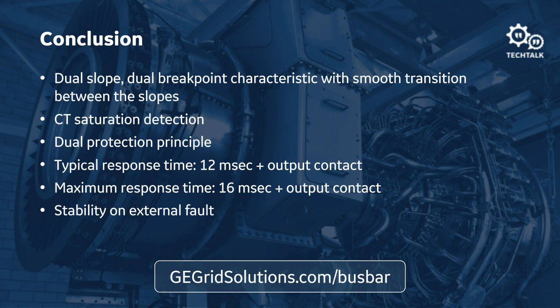Can we do breaker failure protection for each terminal? If you use the low impedance scheme, yes — breaker failure protection can be provided within the same relay for every breaker connected to the bus relay. Can we implement digital substation merging units as IEDs? Yes, we can use merging units, specifically 9-2LE and the hard fiber system. 9-2LE has the advantage of being interoperable with other manufacturers' bus protection relays that subscribe to the standard.